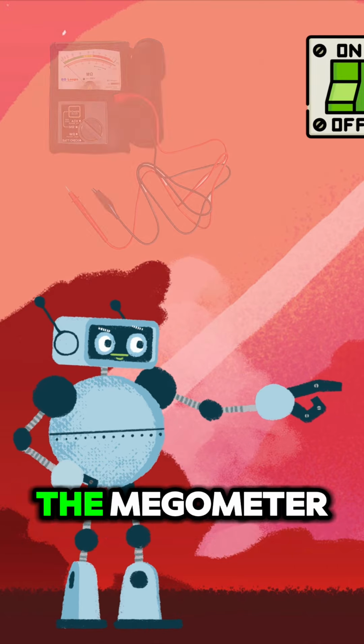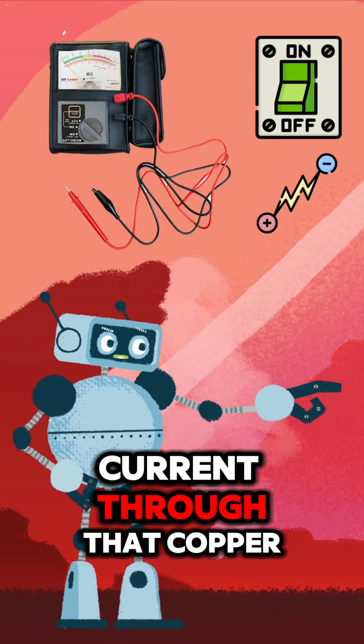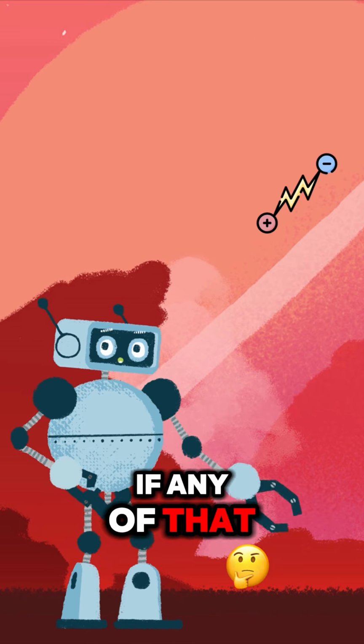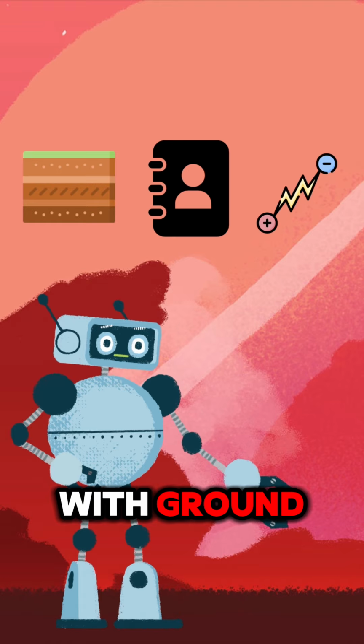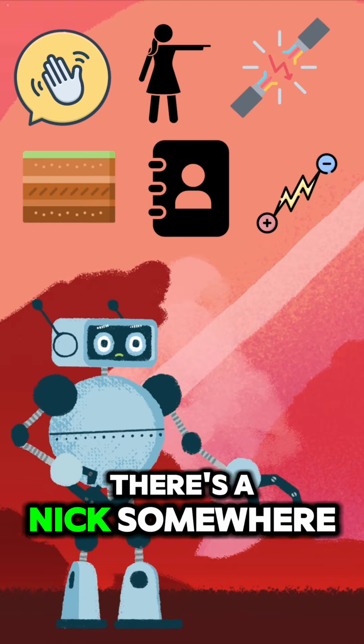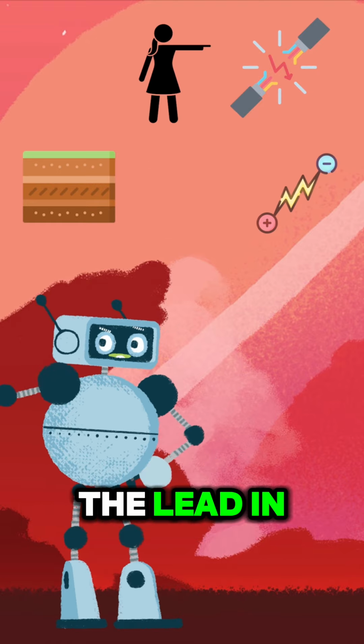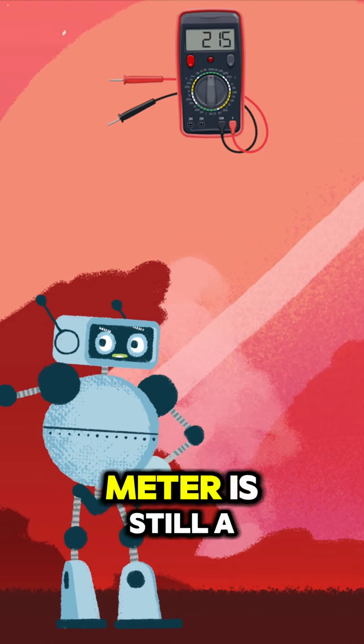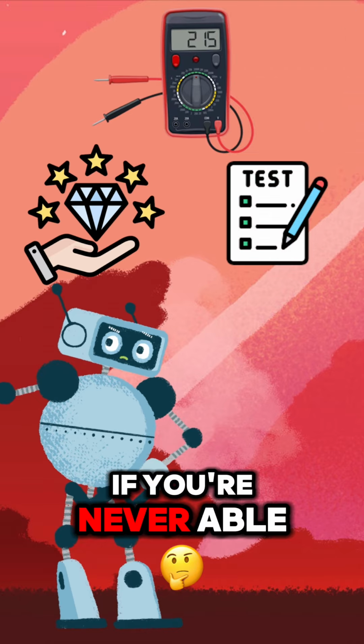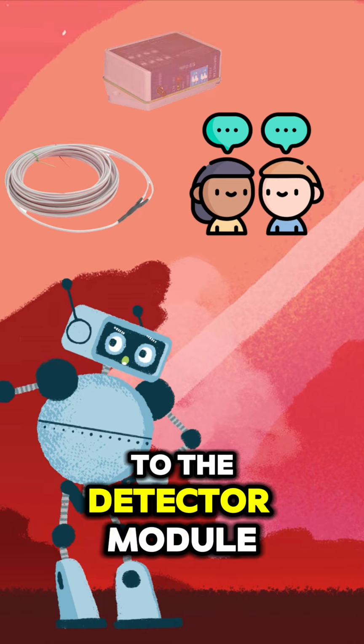When you turn on the megohmmeter, it's going to send current through that copper of the loop to see if any of that current is coming in contact with ground, which is indicating, hey, there's a nick somewhere in the loop or the lead-in. Now, don't get me wrong, a volt ohm meter is still a valuable test if you're never able to get the loop to communicate to the detector module.